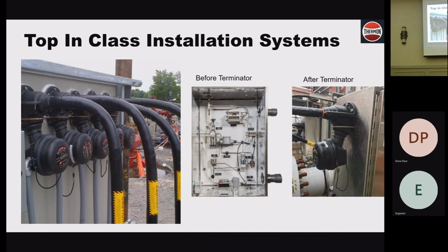We're going to get into the installation part first, then we'll get into that part of it. Again, yesterday it was mentioned that the number one cause of failure of bundles is typically installation. We've seen everything in this business, especially with CEMS bundles. The biggest problem I've seen is people installing them who've never installed them before, and they stretch the bundles. One benefit of how we build our bundles is we spin them, which helps keep the core of that bundle together in one piece. If you guys using stainless steel tubes, what happens to that stainless steel when you get it up to 375 degrees or whatever?